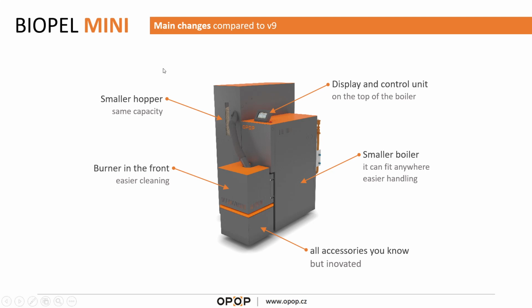The one big difference is also that the burner is in the front of the boiler. So right now it is actually easy to access the burner, to clean it, to see the combustion. You just open the door here and you can see the burner grate, you can see the ashes on the grate, and you can clean it in a few seconds without the need to remove the burner from the boiler, which was the case with the V9 Premium version. On the top there is a display and control unit.